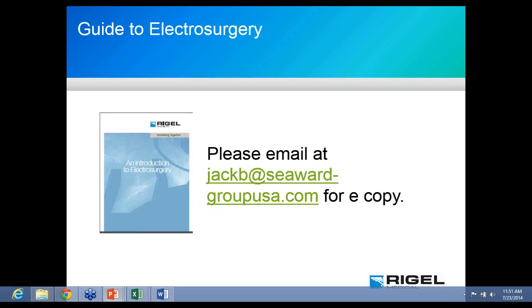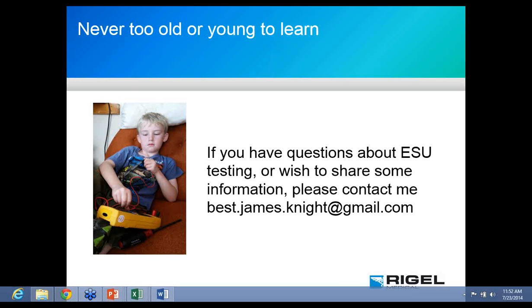So Ryan, the reason you need to is the interference it causes to other medical equipment and the potential harm that it can cause. So if your leakage is too high and the nurse has coiled the ESU's cable around a pole in the OR, she's created a transformer. And the surgical table has a whole lot of ferrous iron, steel in it.